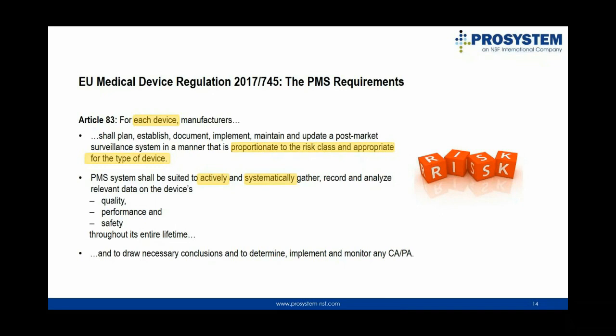So Article 83 asks each manufacturer to plan, establish, document, implement, maintain, and update a PMS system for each device. It needs to be an integral part of the quality management system as referred to in Article 10, Section 9, and must contribute to the quality, safety, and performance of the device. When setting up the system, make it fit to your product's risk classes. The effort for low-risk devices does not have to be as high as for high-risk devices.